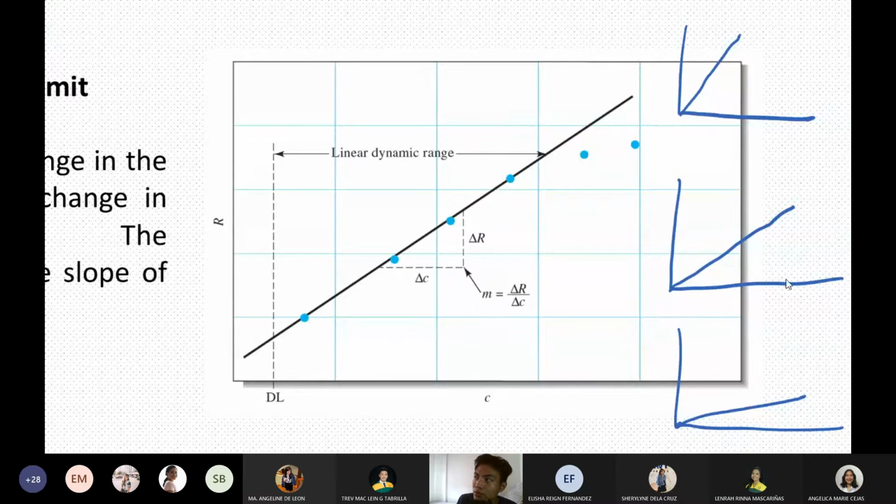So, this is the common calibration curve. Usually, it has an angle of 45 degrees. No? And this is good for micro and major analysis. It could distinguish quite bigger gaps of concentration compared to this one. Because with this one, a small change in concentration gives a high reading right away, since the slope is so high. However, this one is still somewhat flexible. Okay.